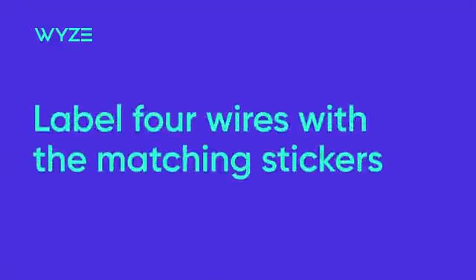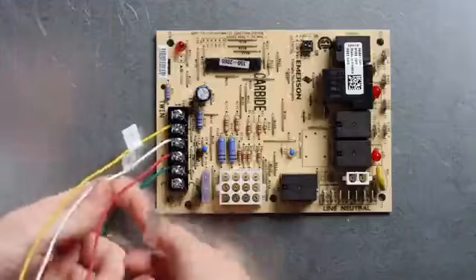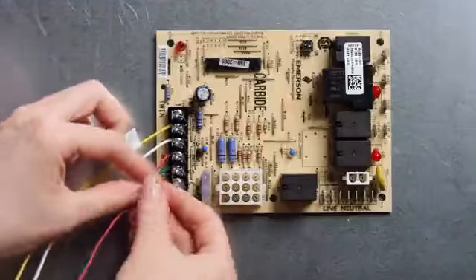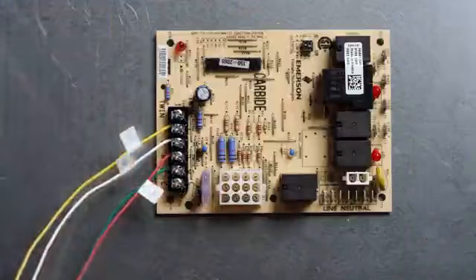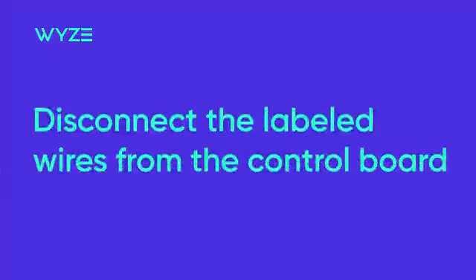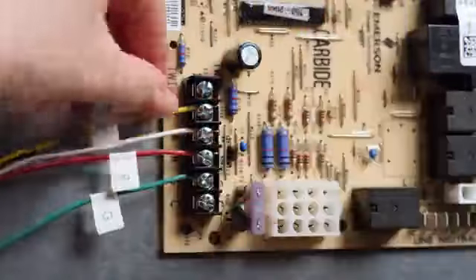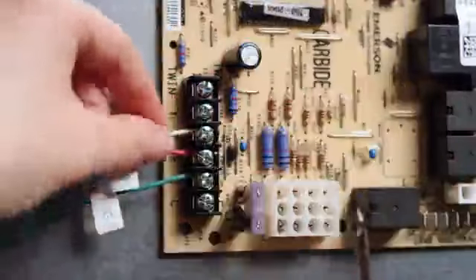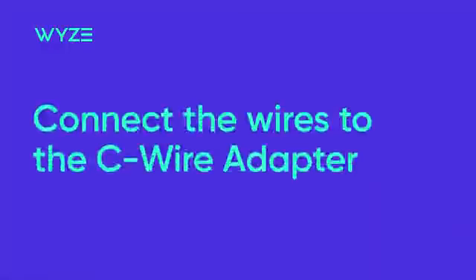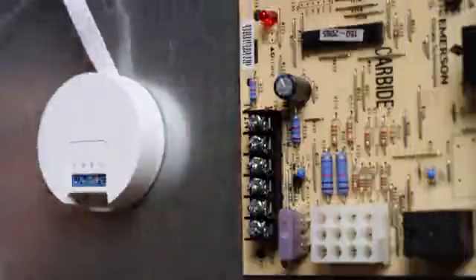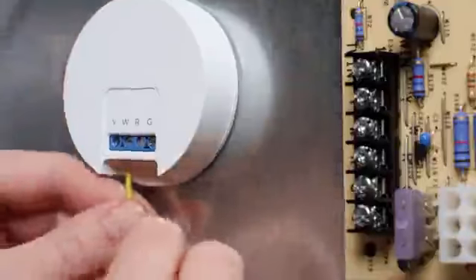Take a picture of your control board wiring for reference. Attach the included labels to the matching wires on the control board. You should see a Y, W, G, and R wire. Once the wires are labeled, you can disconnect them from the control board. You may need to loosen the screws holding the wires to the control board in order to remove them. Mount the C-wire adapter to the inside of your HVAC system using the built-in magnet. Match the labeled wires you just disconnected from the control board to the terminals on the C-wire adapter. Insert each wire into the matching terminal hole and then tighten the screws on top using a flathead screwdriver.